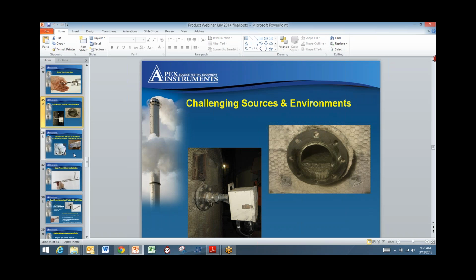What type of maintenance do you have on your probe junction box that you showed there with the heater block? I would say little to none as long as it's functioning. The only maintenance really required, and what I recommend, is when they pull the probe out to change their traps, just use a steel brush and knock any kind of particulate buildup off. Other than that, there's no reason to even go inside that small box on the end, which is kind of like a junction box. There are tees on the back of the sample lines where, if for some reason a trap got stuck or broken, you can take off the back of that T and run a brush all the way down through the probe to clean out any blockage. But it's pretty much just keeping it clean.